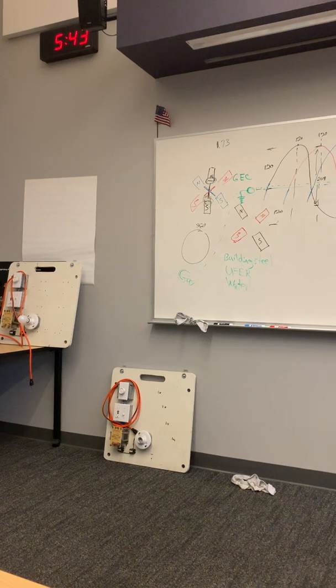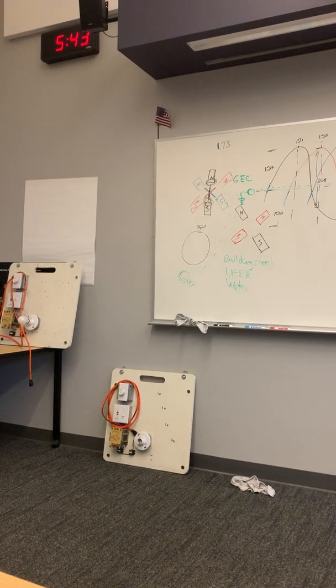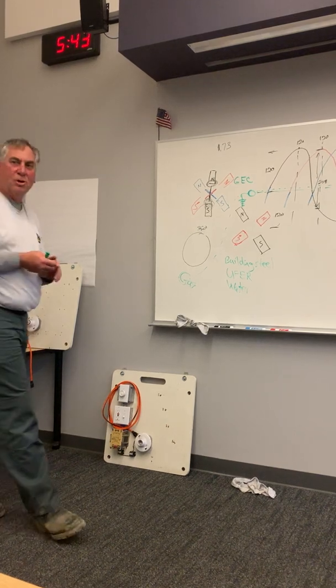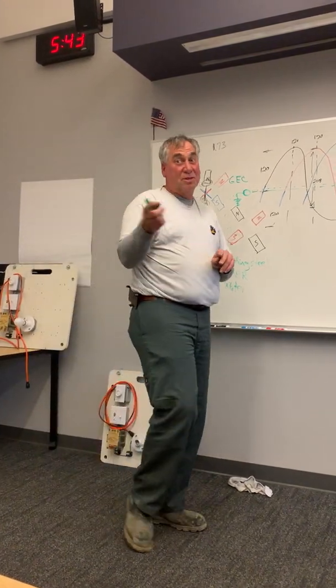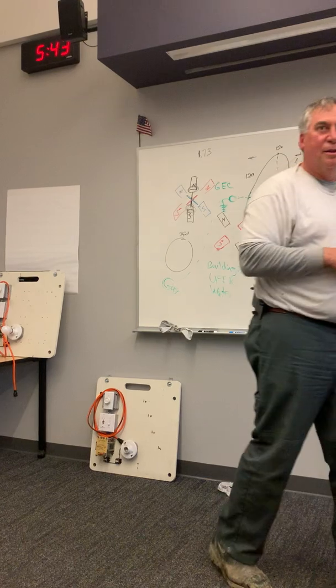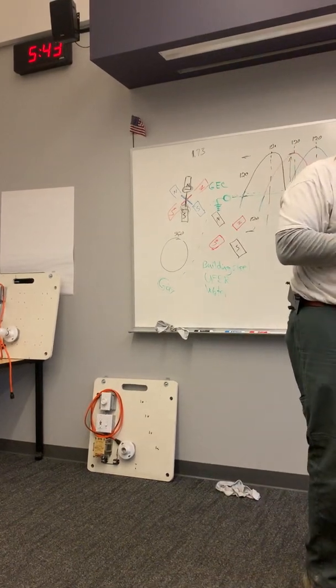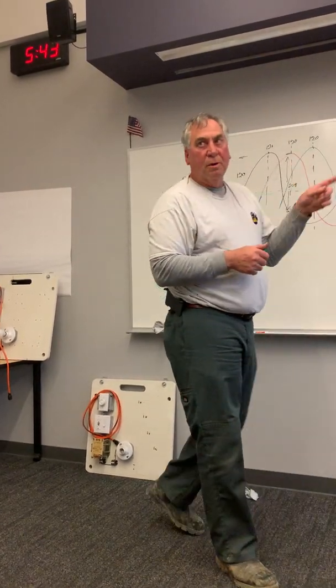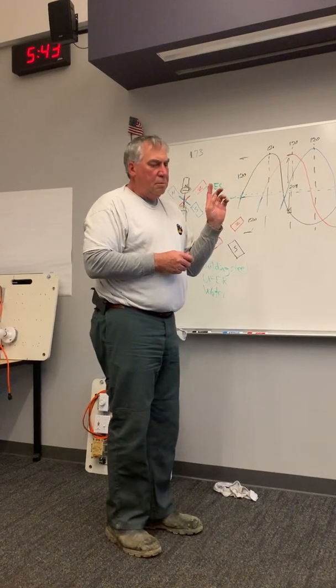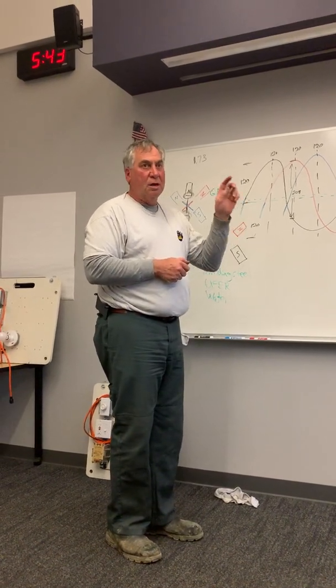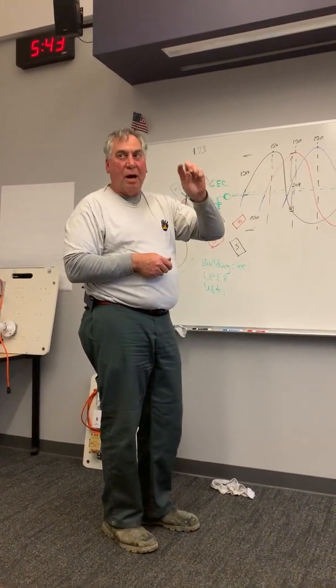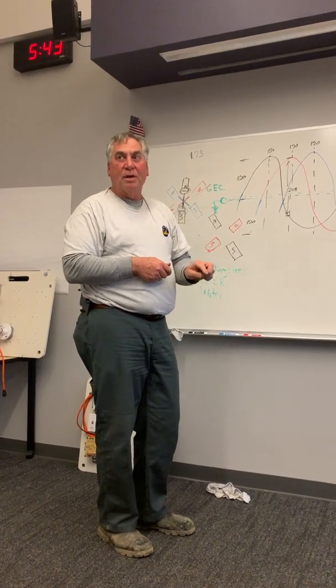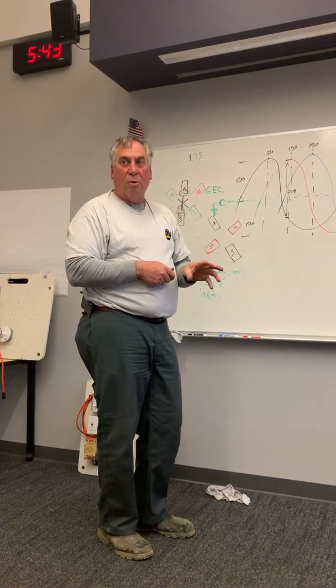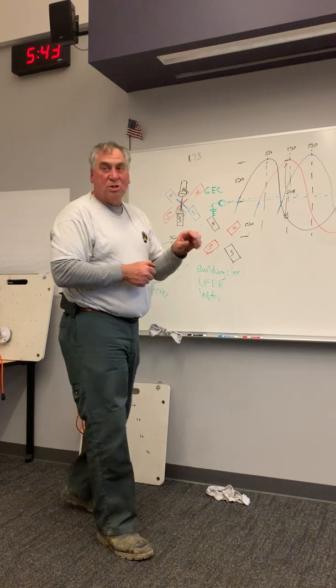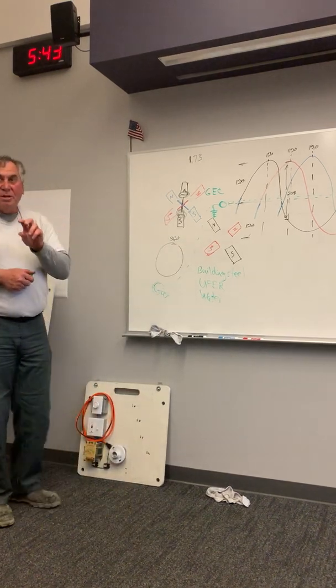Have you ever done a service on a residence? Maybe after this class you would be able to. What they do ask you when you go to put a new service in is that they want to make sure that you bond the hot water, the cold water, and the gas pipe all together, and they want to see that. So what that's doing is bonding all metallic systems.